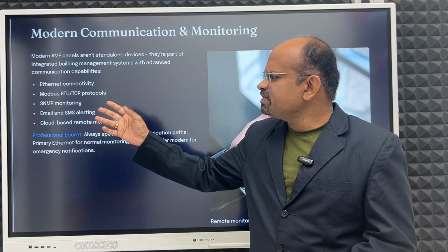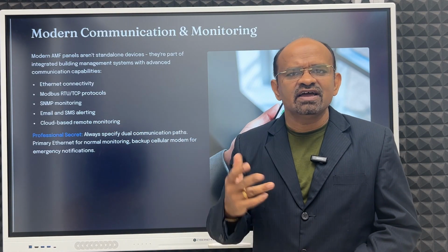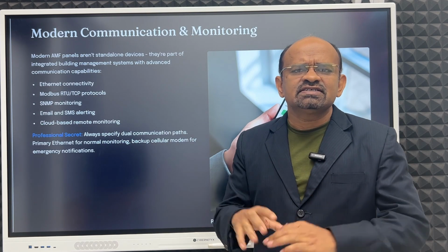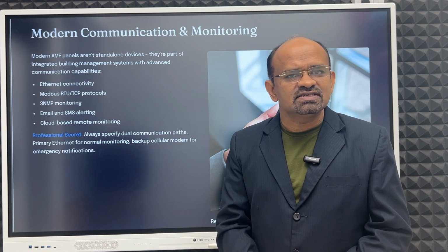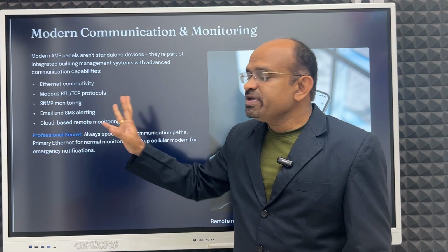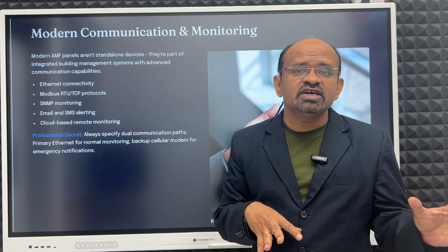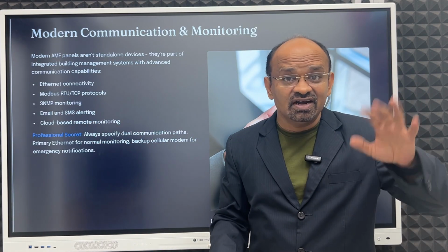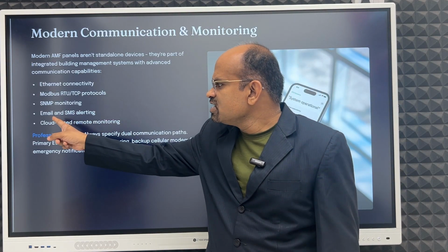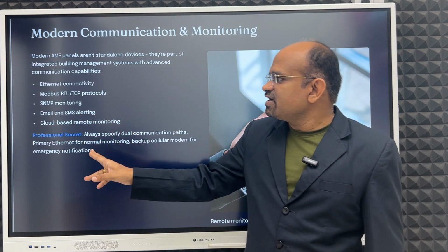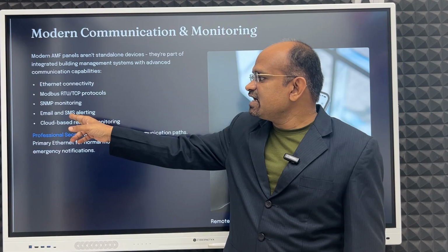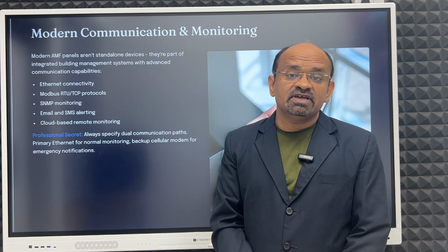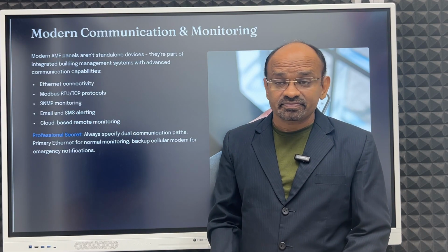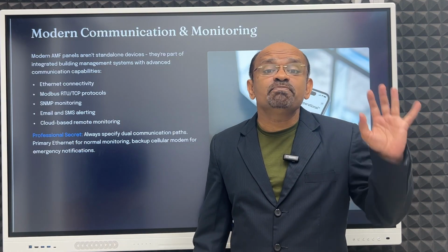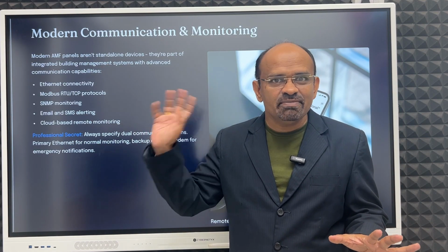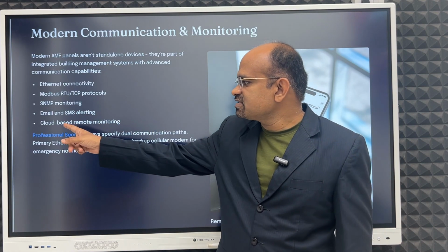Modbus RTU or TCP/IP protocols are also used in fire and all other systems. BMS is generally on these protocols. SNMP is also there. SNMP is used for UPS; the UPS understands that SNMP protocol. So, email and SMS alerting: it will understand and email and SMS the user who is controlling, that there is some problem in the DG set or AMF panel. So it should email or SMS.